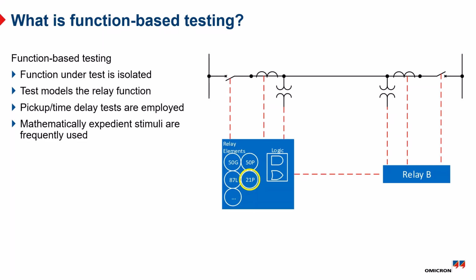Trouble is, if I try to do a pickup test, you'll notice on that single line diagram we have a bunch of different functions on this one input. So if I apply current while trying to test my 21, my time overcurrent elements can also operate. My line differential could operate, etc. So I have to have some way of intelligently isolating that. Also, I have to satisfy my logic, breaker position, all those other things.